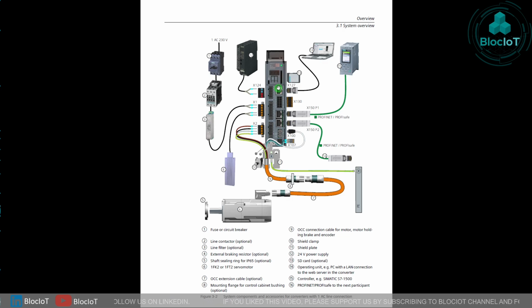And on the drive, there are 3 different Ethernet ports. These 2 ports are just connected together internally, and normally use the first one for connecting to your PLC, and the second port can go to another drive or another PLC or maybe your laptop. And for sure, the drive needs an input voltage. That's why we have this fuse or circuit breaker on the top, and then we have a contactor to maybe cut the power remotely from a PLC if we need to. And then we have an optional line filter, and also we have an external braking resistor if you need that.